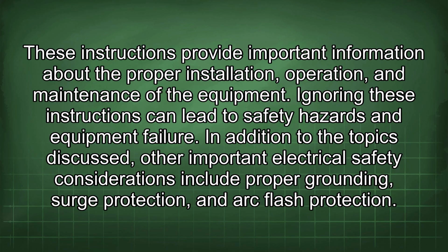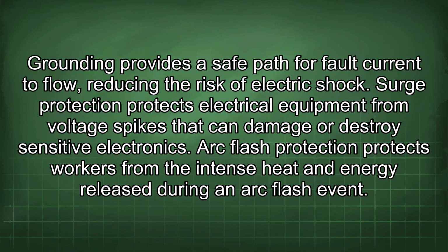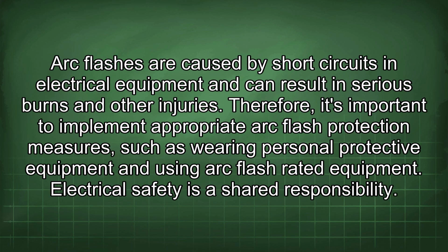In addition to the topics discussed, other important electrical safety considerations include proper grounding, surge protection, and arc flash protection. Grounding provides a safe path for fault current to flow, reducing the risk of electric shock. Surge protection protects electrical equipment from voltage spikes that can damage or destroy sensitive electronics. Arc flash protection protects workers from the intense heat and energy released during an arc flash event. Arc flashes are caused by short circuits in electrical equipment and can result in serious burns and other injuries.